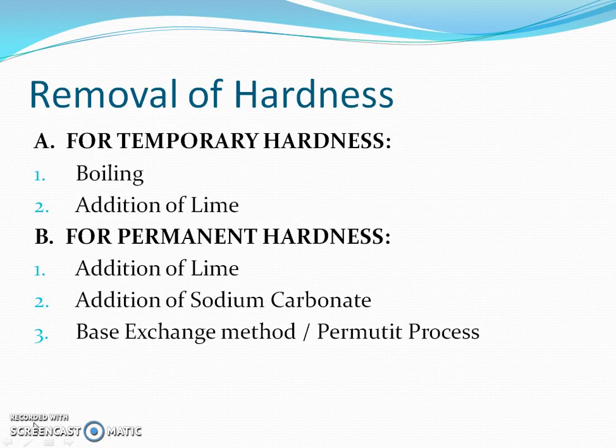As already stated, boiling converts soluble bicarbonates of calcium and magnesium into insoluble ones, which can be removed by mere filtration. Second method for removal of temporary hardness is chemical one, and it is nothing but addition of lime. Lime is responsible for removal of temporary hardness causing salts.